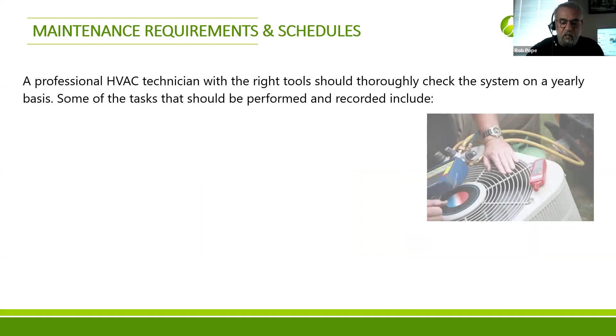So, a service technician once a year, ideally, twice a year if it's a complex system, and at the very least once every couple of years. You want to check for adequate airflow and external static pressure. You want to check for temperature rise between supply and return air, inlet gas pressure, and clock the meter on a dual fuel system. Inspect and clean the evaporator coil. Check the refrigerant for leaks and top it up if there's any lost refrigerant. Inspect, clean, and tighten all the electrical connections. They can get loose. Any tiny little bit of vibration anywhere in the system could potentially affect the connection and the contact of a wire to a terminal that wasn't tight enough in the first place.